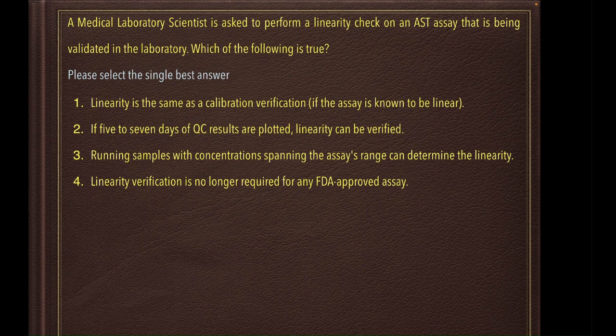1. Linearity is the same as a calibration verification if the assay is known to be linear. 2. If 5 to 7 days of QC results are plotted, linearity can be verified. 3. Running samples with concentrations spanning the assay's range can determine the linearity. 4. Linearity verification is no longer required for any FDA-approved assay.